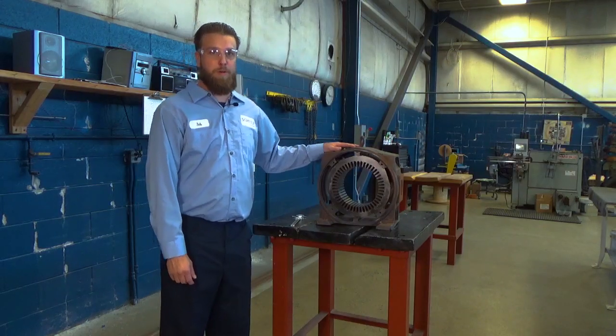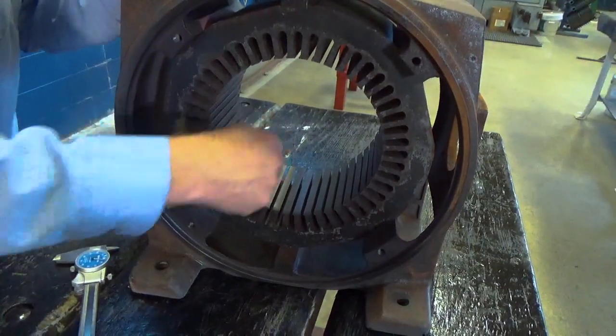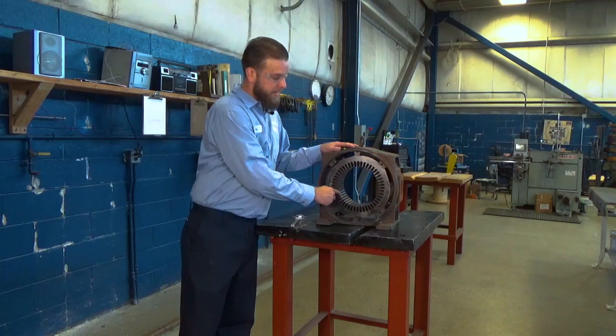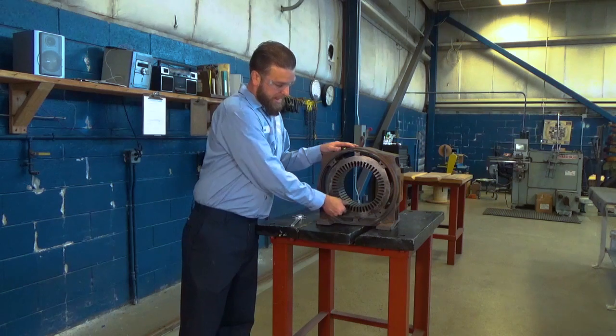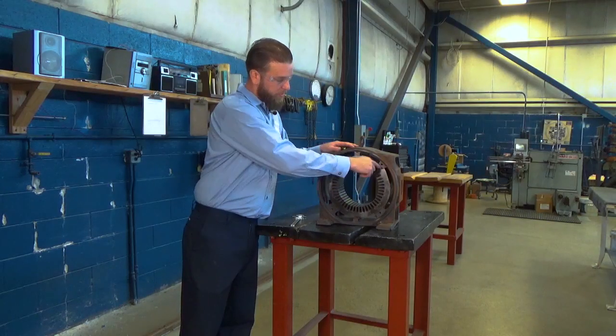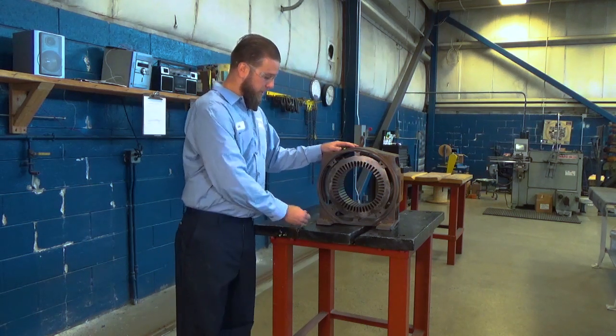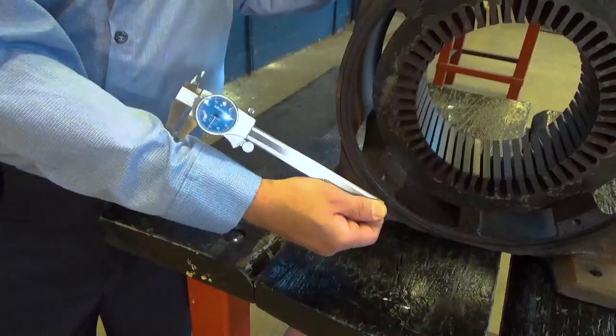In our first steps in the recore procedure, what we're looking for is our core length, inside diameter, slot depth, back iron, and our overall outside dimension. We use a calibrated caliper for those dimensions.